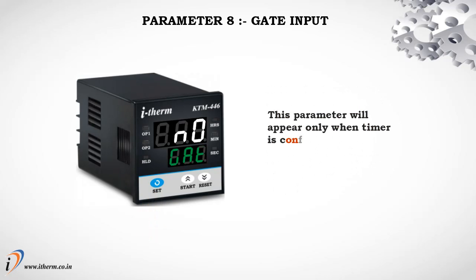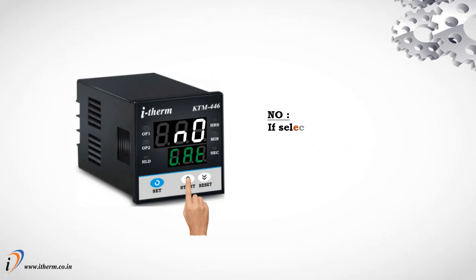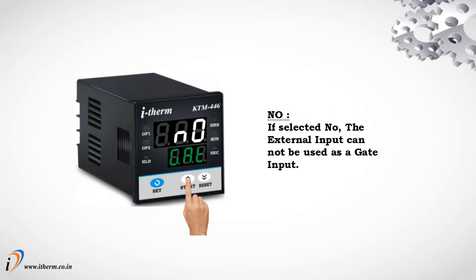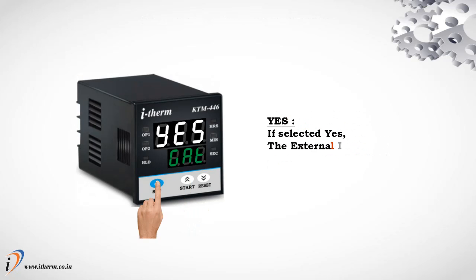Parameter 8, gate input. This parameter will appear only when timer is configured for either power on start or front start. If selected no, the external input cannot be used as a gate input. If selected yes, the external input can be used as a gate input.